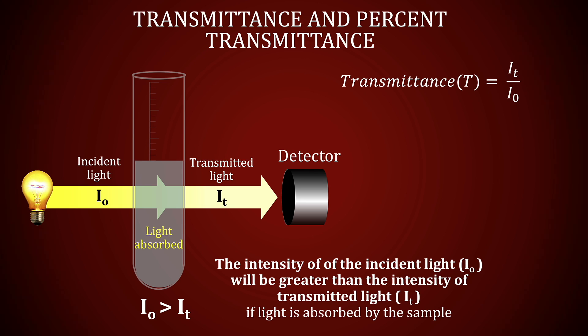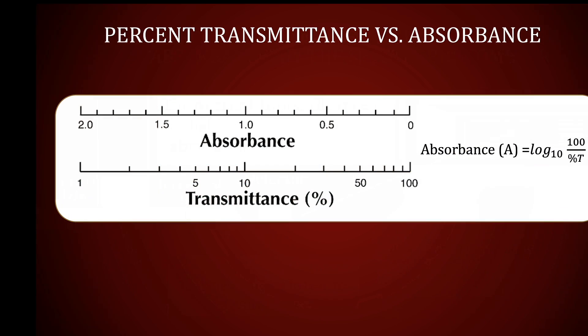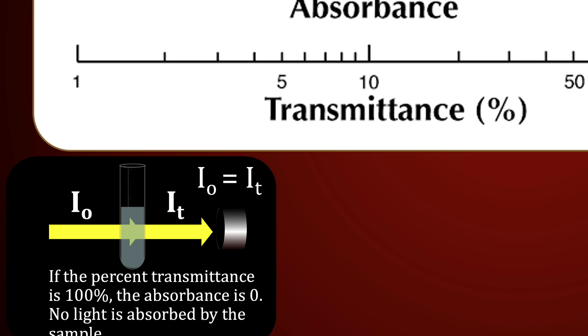The fraction of the light reaching the detector is called transmittance. The percent transmittance is the transmittance times 100. The percent transmittance is converted to an absorbance measured by the device. The percent transmittance is inversely proportional to the absorbance — in short, a higher transmittance means a lower absorbance. For example, if the percent transmittance is 100%, this means the light passed completely through the sample with no absorbance at all.